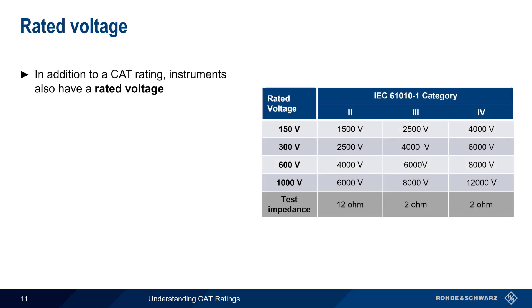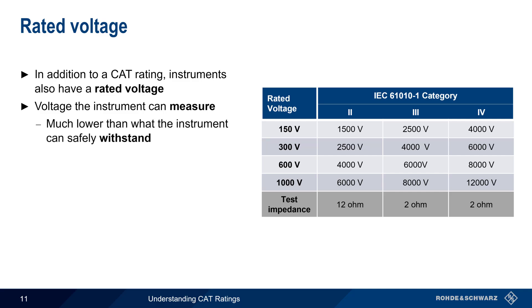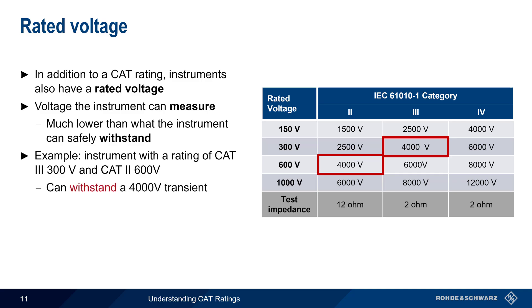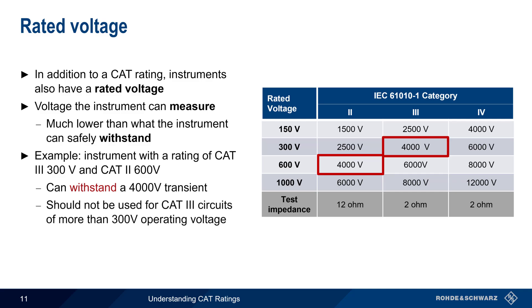In addition to a CAT rating, measuring instruments and accessories will also have a rated voltage. This is the maximum voltage that the instrument can measure, but note that this is a much lower voltage than what the instrument can safely withstand. For example, consider an instrument with both a CAT 3 rated voltage of 300 volts and a CAT 2 rated voltage of 600 volts. Although the instrument can withstand a 4000 volt transient in both cases, it should not be used for CAT 3 circuits with an operating voltage of more than 300 volts, or a CAT 2 circuit with an operating voltage of more than 600 volts. And since it does not have a CAT 4 rating, it should never be used in a CAT 4 environment, regardless of the voltage.